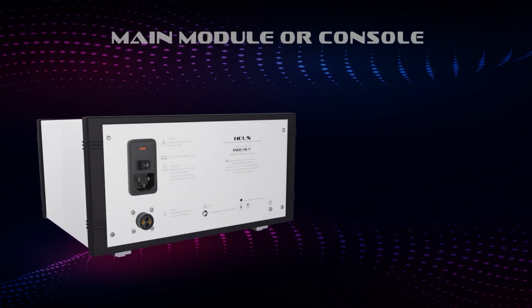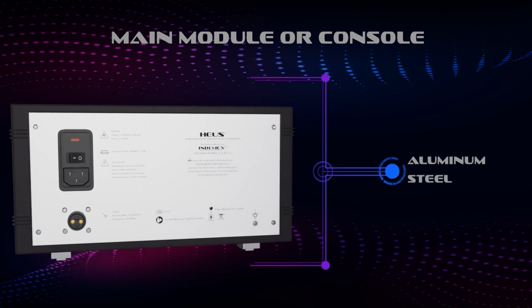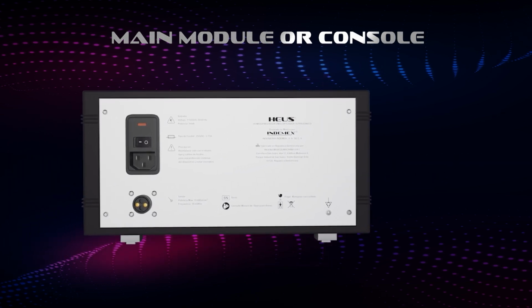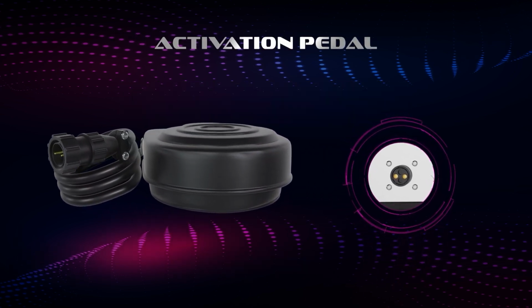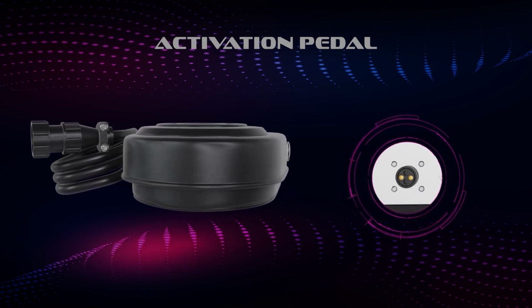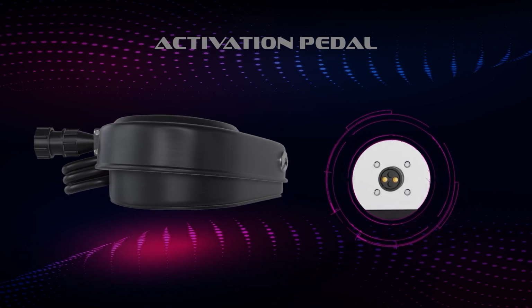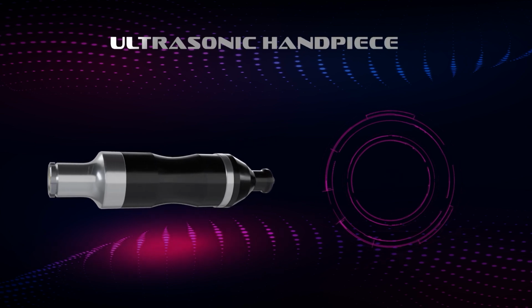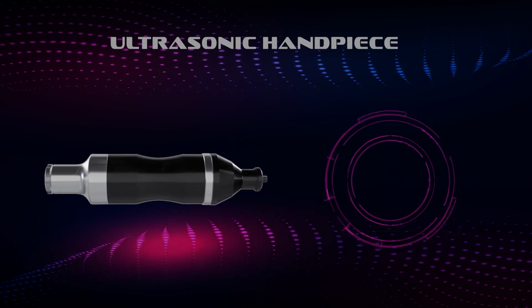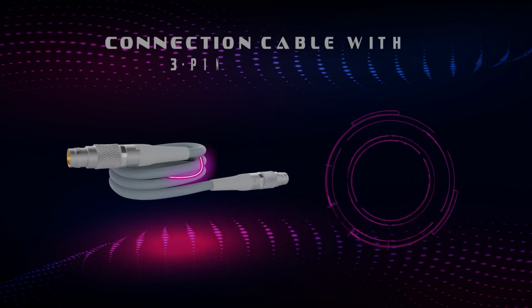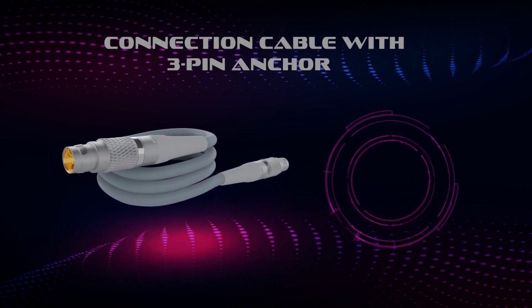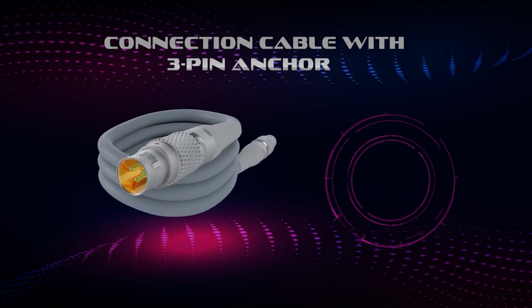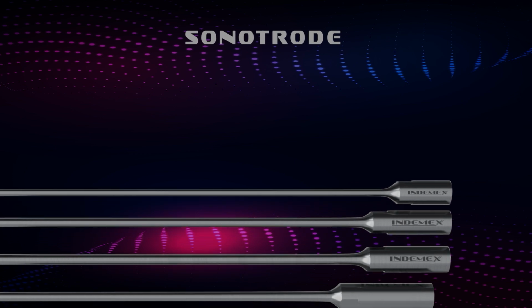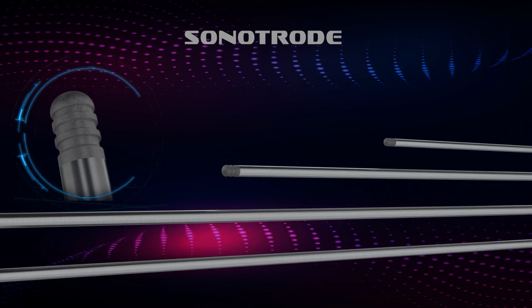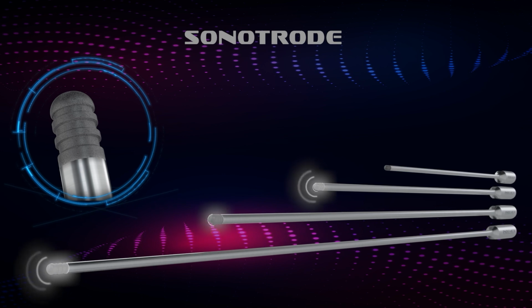Main module or console. Made of aluminum and steel, it is responsible for generating and distributing different types of energy. Activation pedal. Necessary for operation, as without it, it will be impossible to activate the energy output of the device. Ultrasonic handpiece. Responsible for converting electrical energy into ultrasonic waves. Connection cable with 3-pin anchor. Responsible for conducting energy to the handpiece. Sonotrode. Body that carries ultrasound from the handpiece to the tissue, which vibrates at 40 kHz.